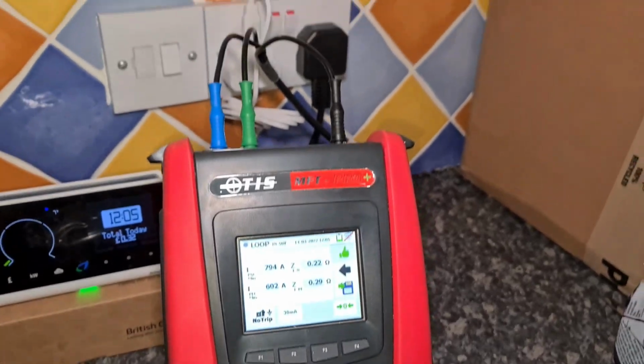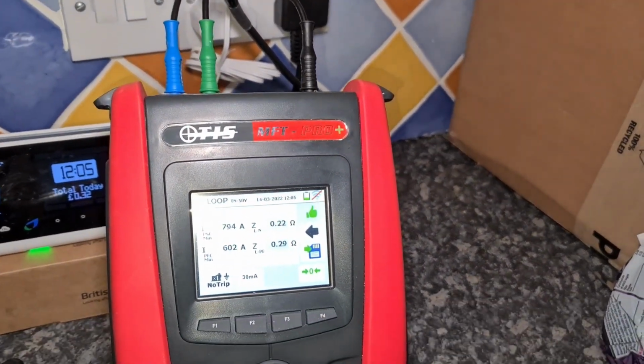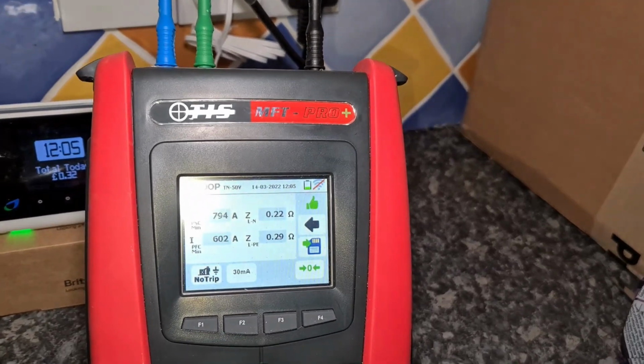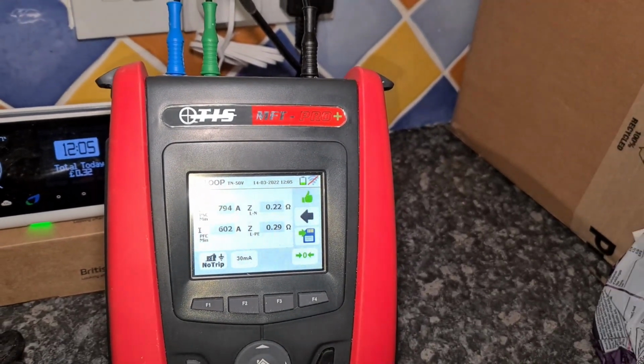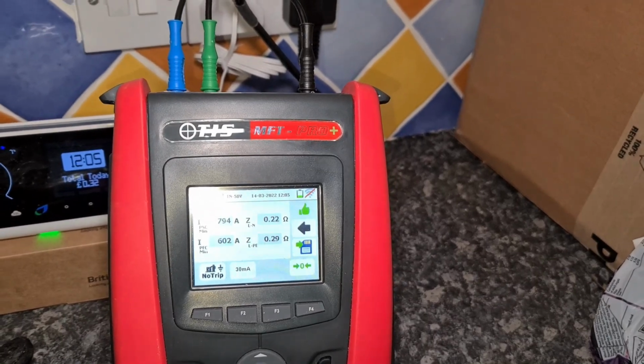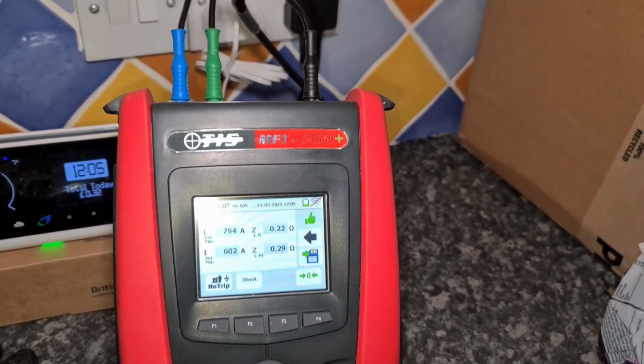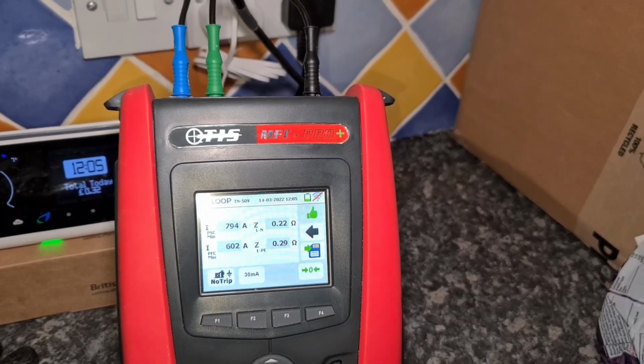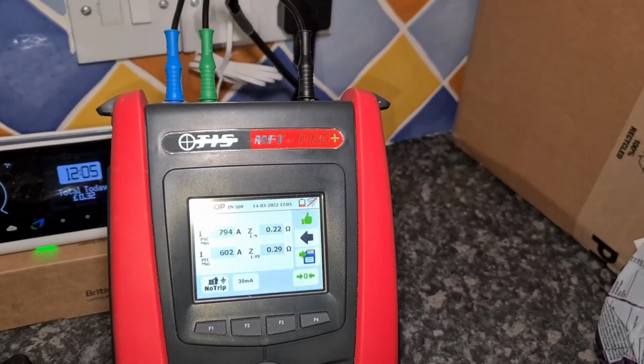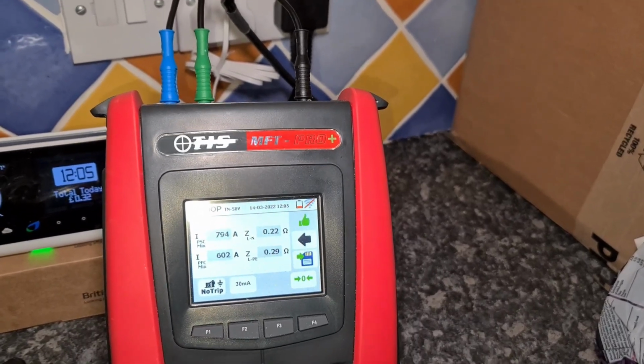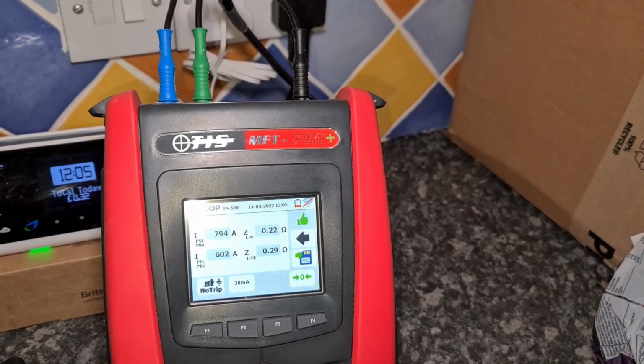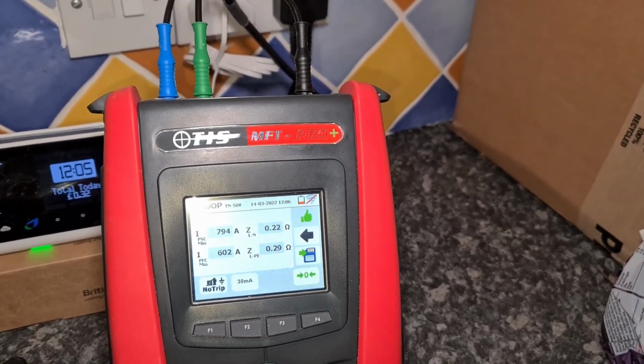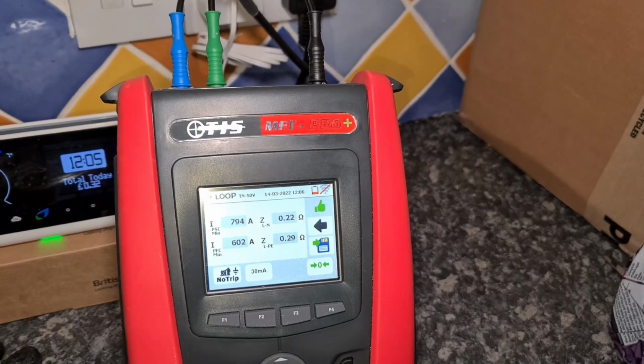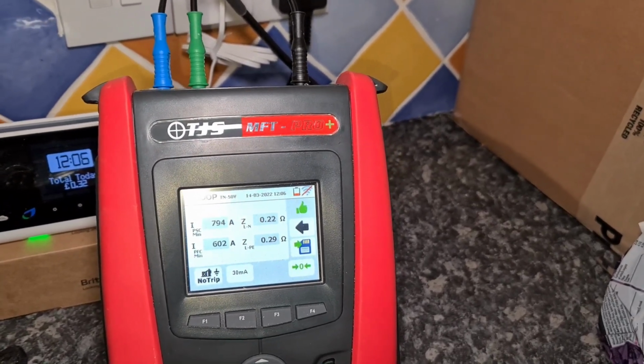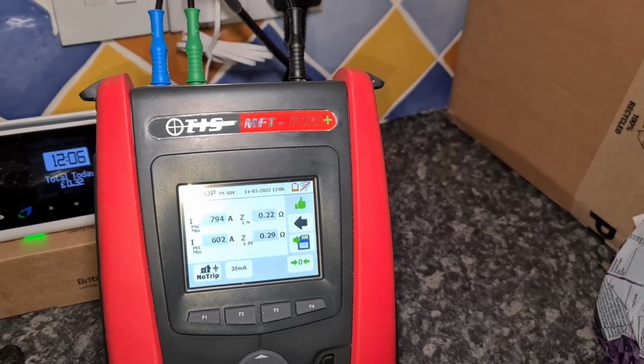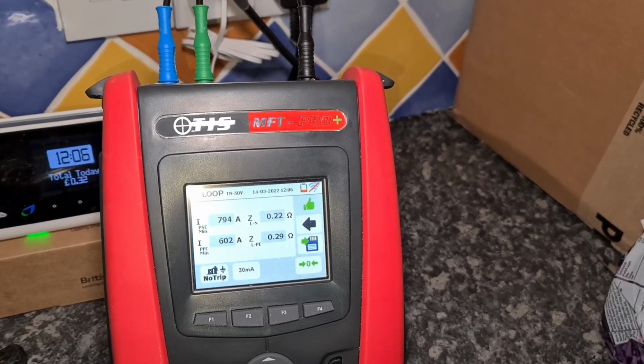Okay, so this is the socket circuit on that utility ring final that I tested earlier in this video, and you'll see it's given us an earth fault loop impedance value of 0.29 ohms. Now that's a little bit under what the calculation tells us it should be - I think it was 0.18 on the R1, R2 for this circuit, and then we had around the same again for our ZE, so we should be around 0.36, 0.37, something like that, and we're obviously underneath it. That's because we've got the bonds in place. This is a true impedance path of this circuit carried out under live conditions, so we know we have an accurate value - it's not based on calculations.